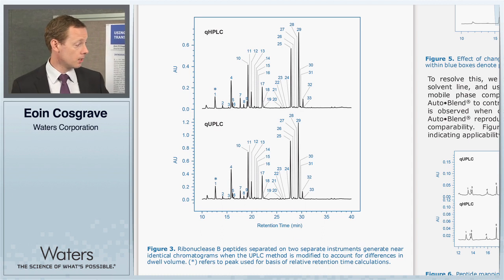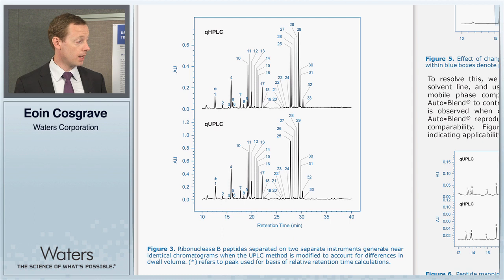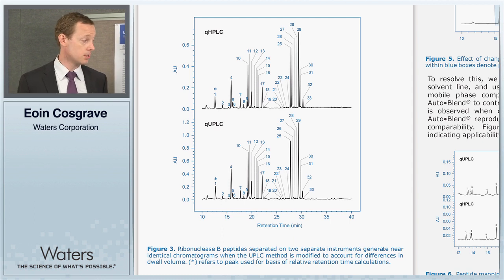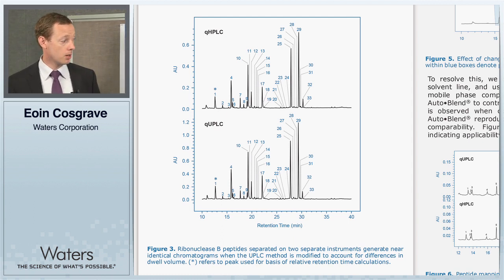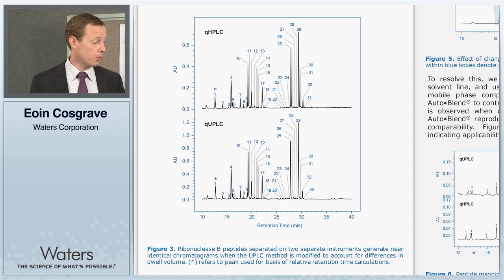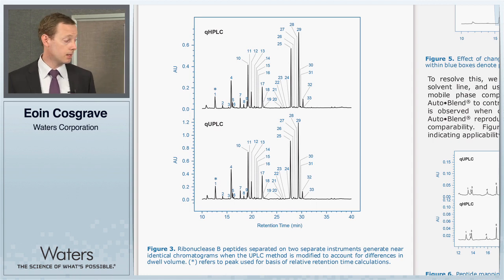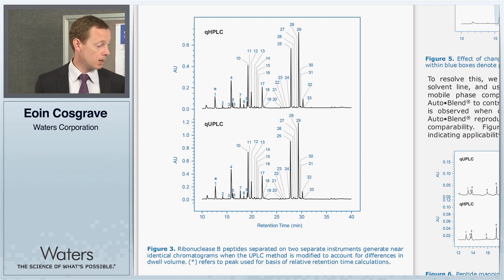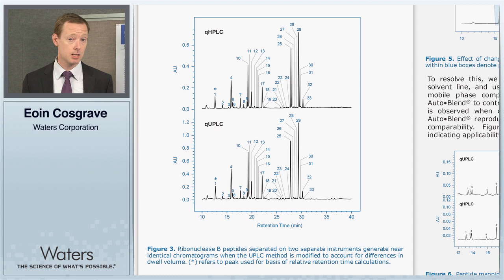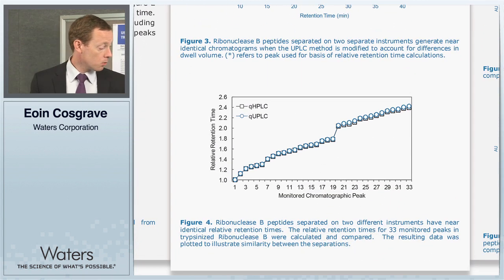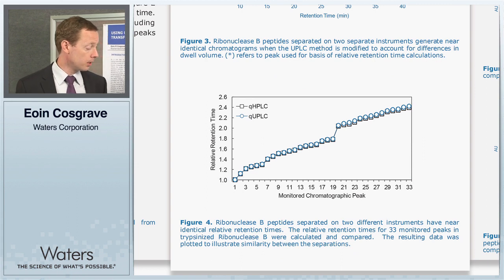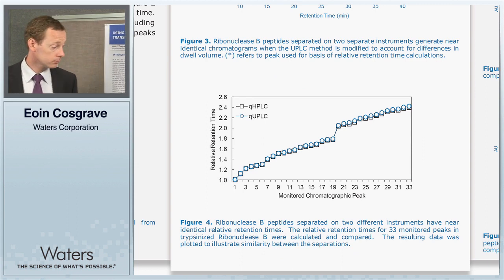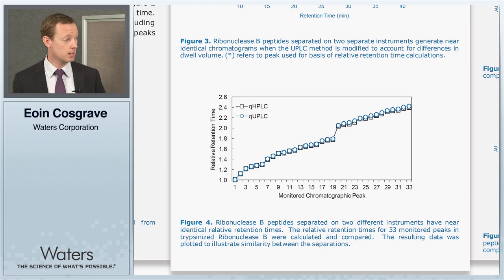In figure three, the top chromatogram is the legacy HPLC instrument chromatogram of a tryptically digested ribonuclease B, and here we monitored 33 peaks across that profile. When we take that same method and include the gradient start offset, we get the exact same relative retention times using the H-class Bio compared to the legacy HPLC instrument. This is quantified in figure four, where the relative retention times of these two profiles overlay quite nicely.